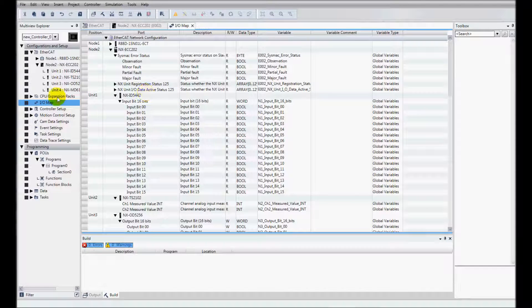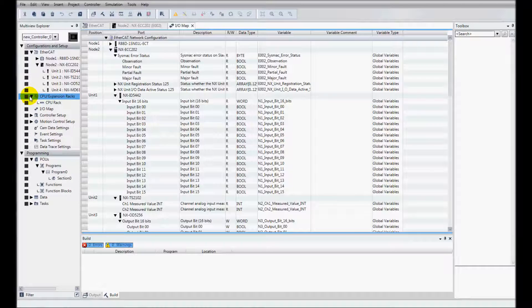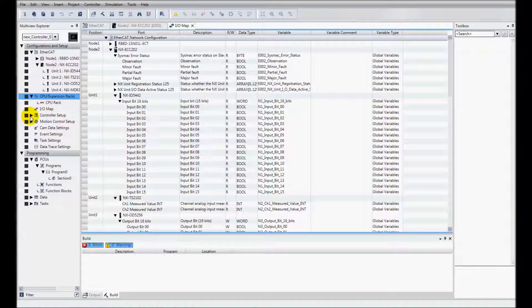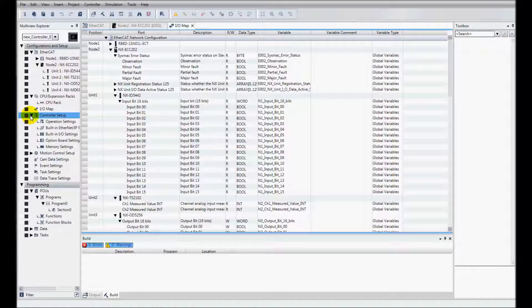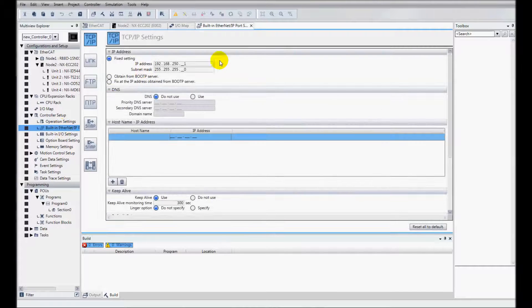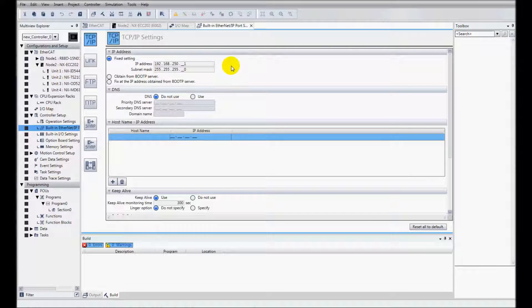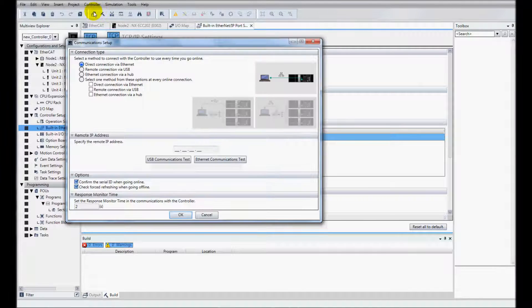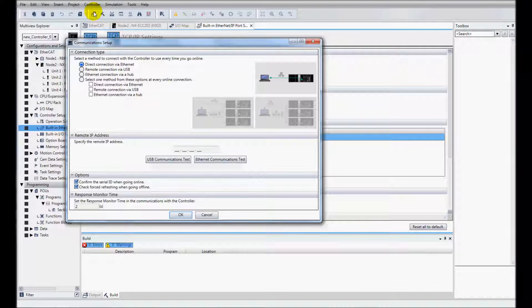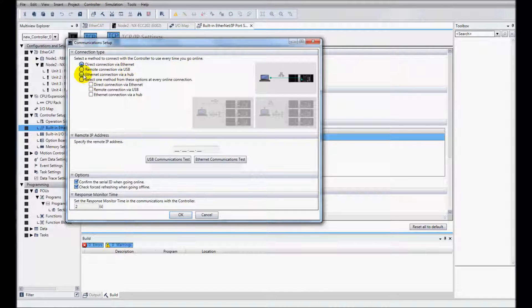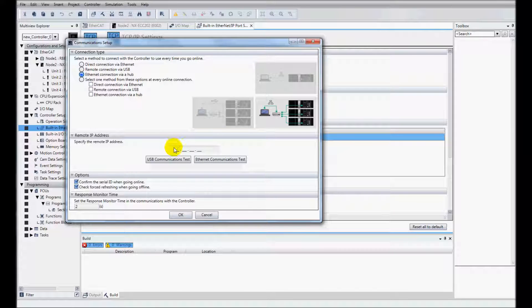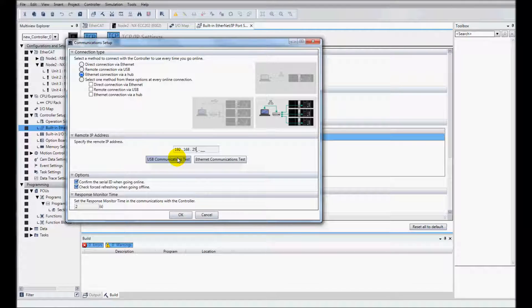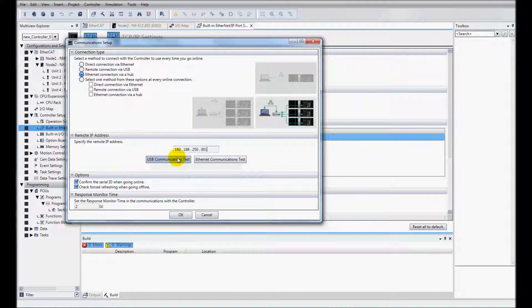Next, I'll go to the CPU and go to my controller setup and my built-in Ethernet IP. IP address is 192.168.250.1. And I'll go to my controller communications setup and type in that address, 192.168.250.1.